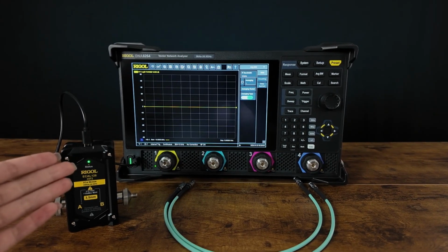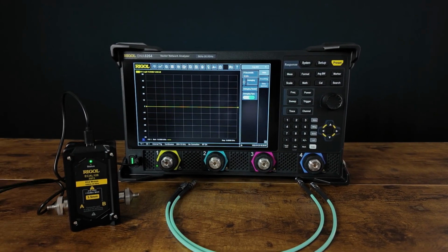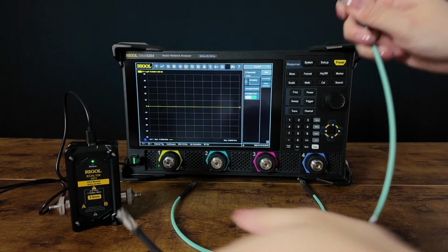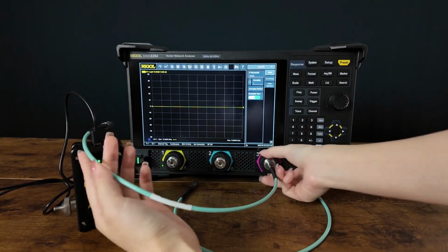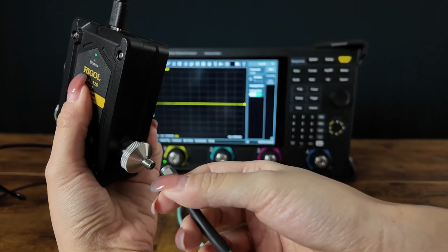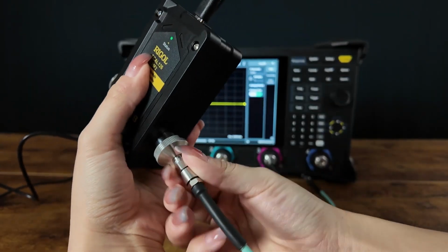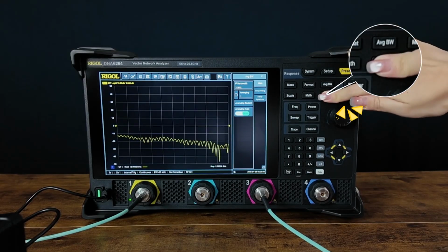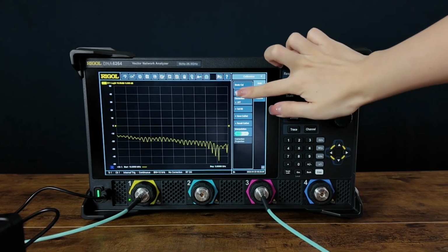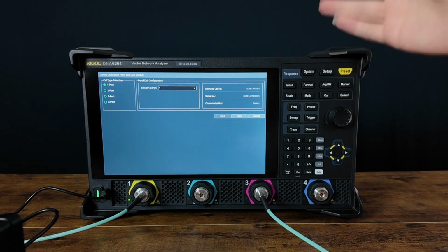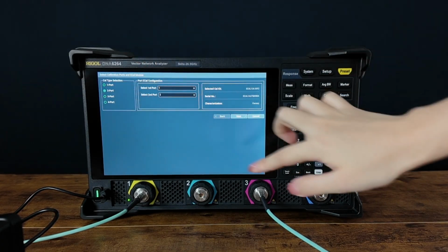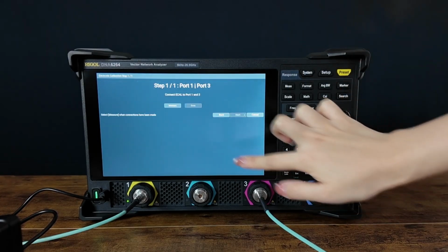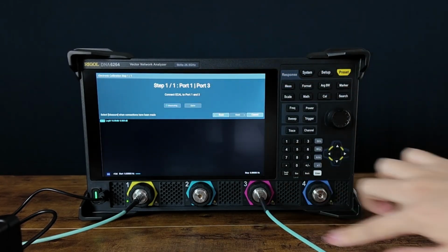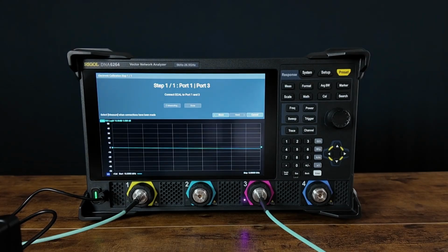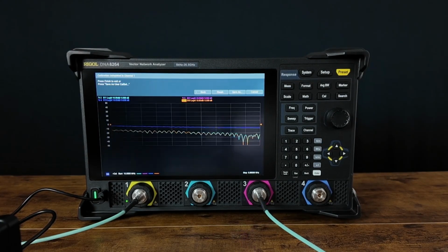Now, the light turns green, which means the preheat is ready. And let's connect the SMA cable to the port. And then connect the cable to the ECal. Now, let's press the Cal button. And then choose ECal. And then follow the on-screen prompts. Next, click Measure. See, the electronic calibration is done now.